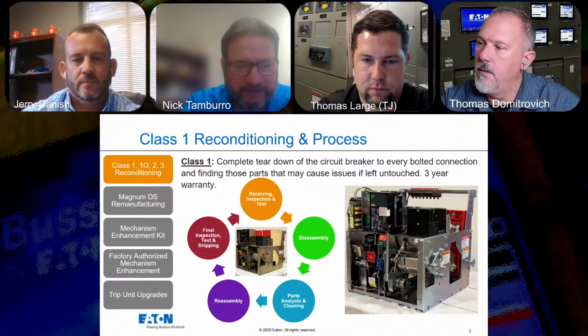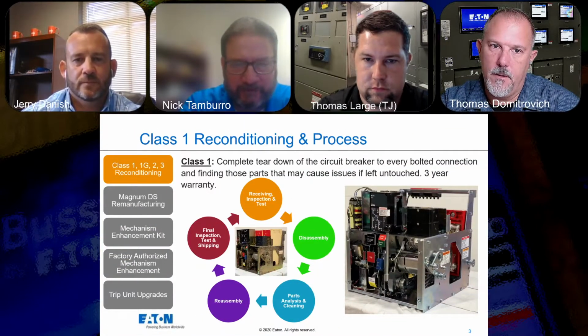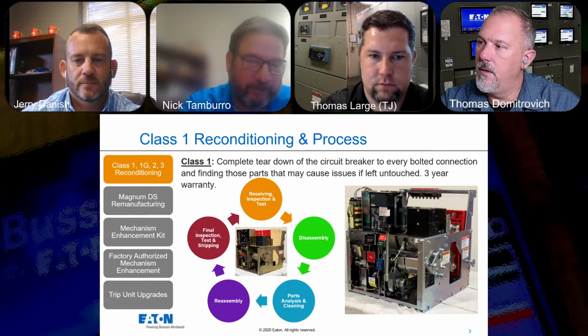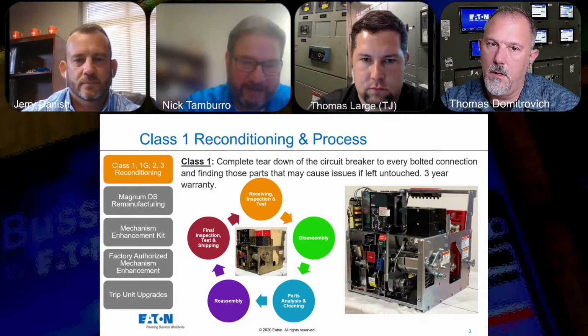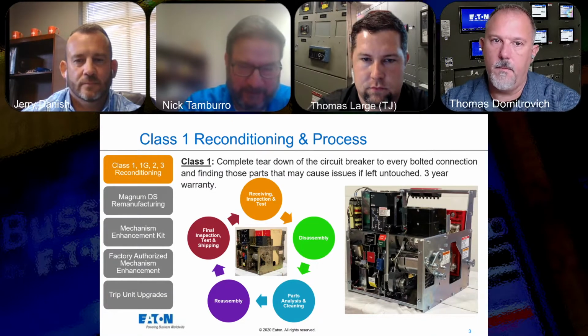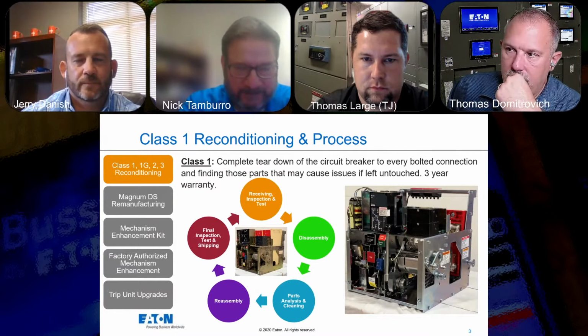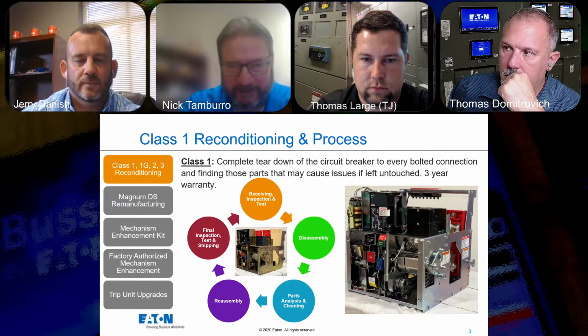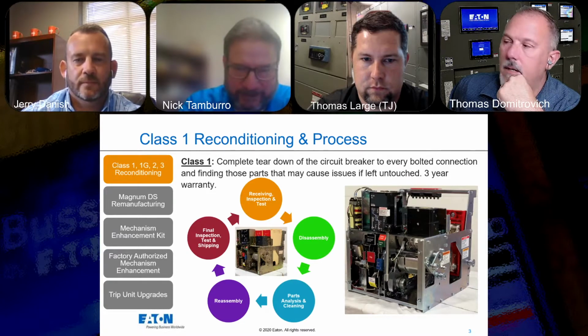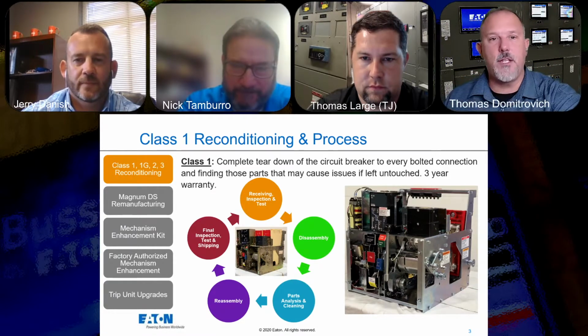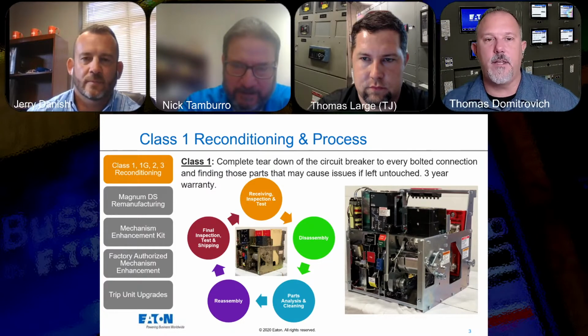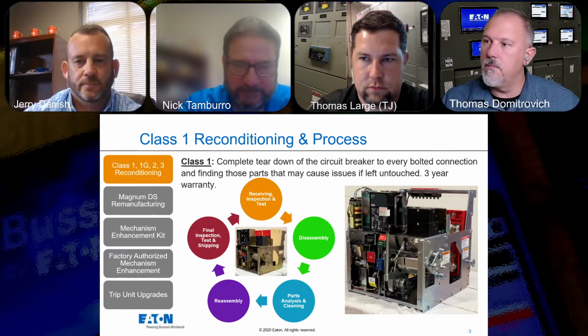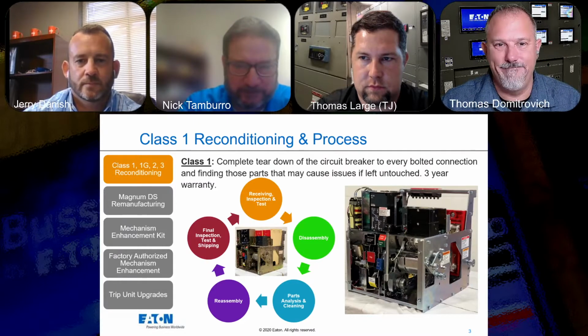I'm actually performing that here for Chicago Airport, 99 breakers as part of a class 1 reconditioning. It's full blown class 1 reconditioning, MEK, which we spoke about earlier. Yep, they want the MEK Mech. It's a Digitrip 910, converted from manually operated to electrically operated and ARMS. So it has arc flash reduction maintenance switch. It's like the whole package. Is this something that they send back to you, or can you do this at their facility? We do it here at the PBRC. That would be too intense to do in the field. Yep.